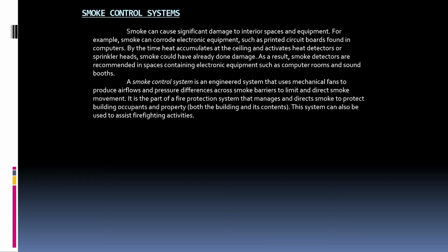Smoke can cause significant damage to interior spaces and equipment. For example, smoke can corrode electronic equipment, such as printed circuit boards found in computers. By the time heat accumulates at the ceiling and activates heat detectors or sprinkler heads, smoke could have already done damage. As a result, smoke detectors are recommended in spaces containing electronic equipment such as computer rooms and sound booths.